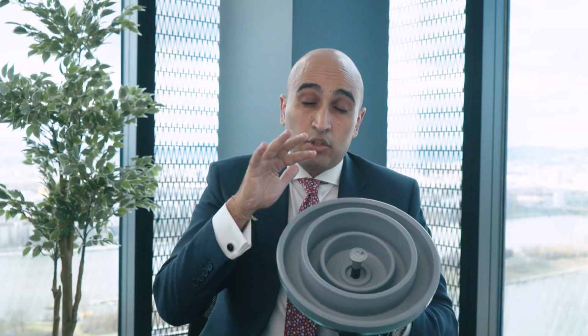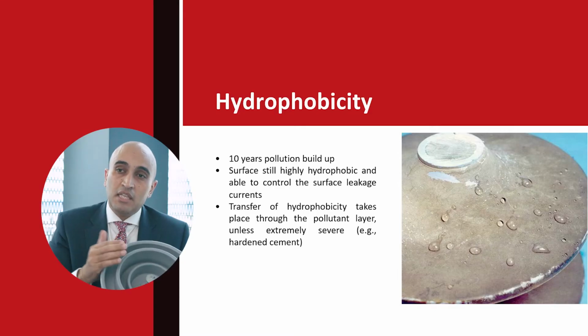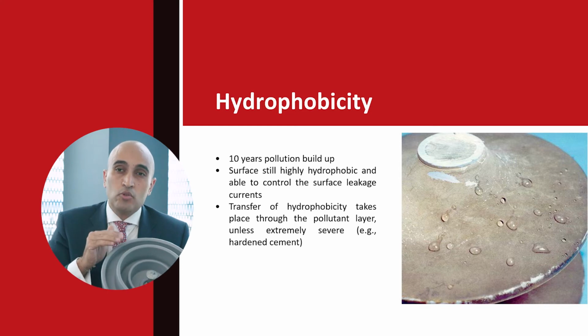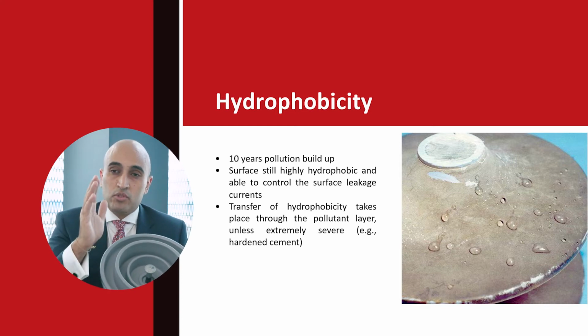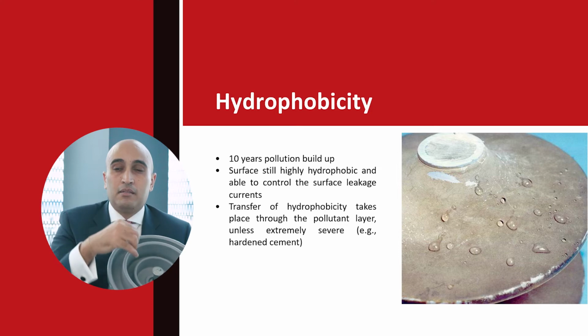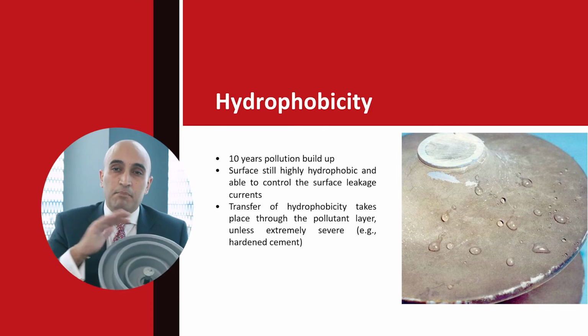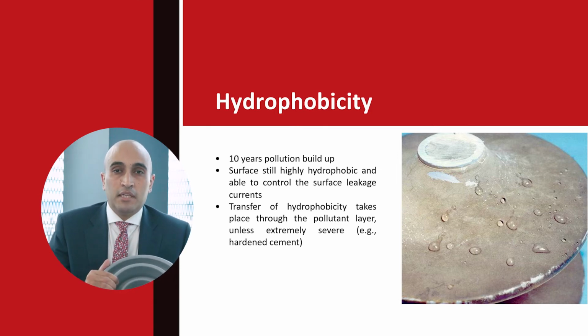What we call hydrophobicity transfer through the contaminant layer is this: even though the insulator will be coated with contaminants in its service life, the low molecular weights will travel through the bulk of the coating and will keep encapsulating the contaminants, preventing them from leaking currents.